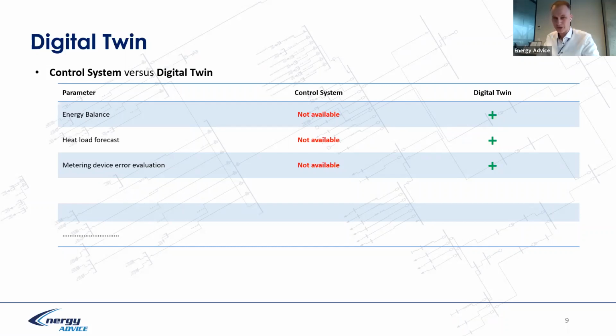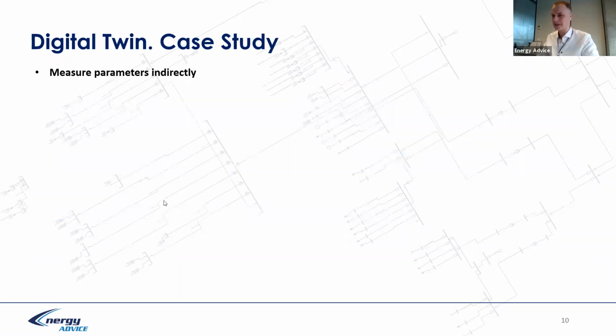Because in the digital twin we describe the boiler as a set of equations. What is the number? Maybe 300 equations which describe the boiler, and they are solved at the same time, so we can correctly understand the fuel calorific value, the water content, and how much fuel we should push to the furnace to produce heat according to the heat demand, or steam or water demand.